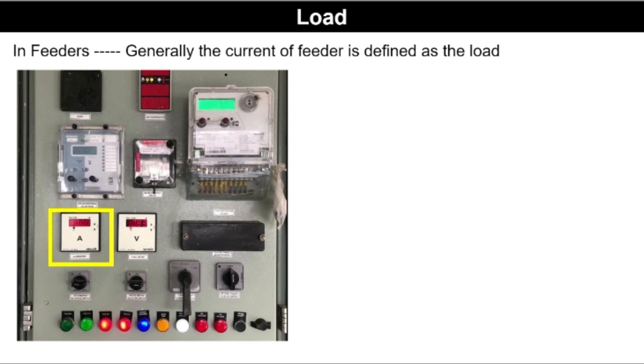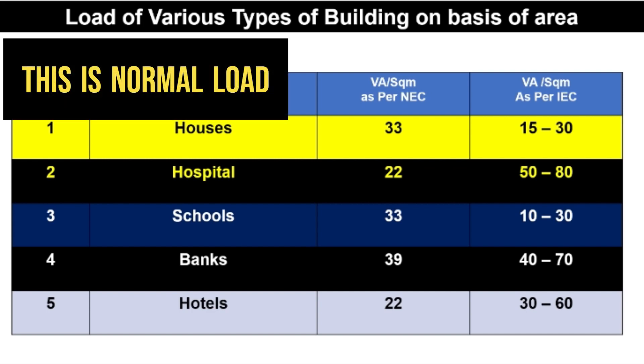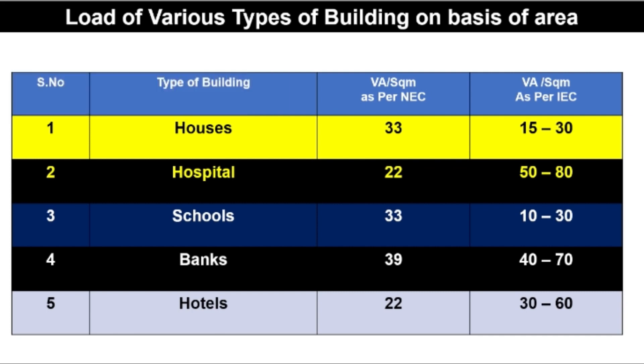The load of various buildings as per NEC and IEC standards are: for a house, as per NEC, Volt-Amperes per square meter is 33, and as per IEC it is 15 to 30. For a hospital, it is 22 (NEC) and 50 to 80 (IEC). For schools, it is 33 (NEC) and 10 to 30 (IEC). For banks, it is 39 (NEC) and 40 to 70 (IEC). For hotels, it is 22 (NEC) and 30 to 60 (IEC).